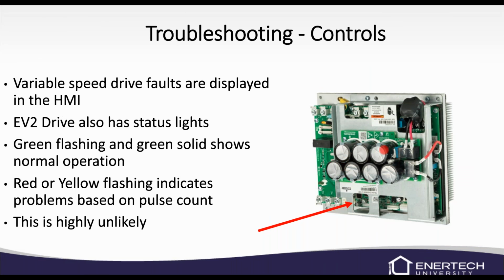This is the variable speed drive for the compressor here, and it does have status lights. Green flashing and green solid show normal operation. The red or yellow flashing indicates a problem that's based on pulse count. I do not know what those pulse counts mean, so if you do get that, just write it down and give me a call, and I'll get in touch with Jeff Croxall, our engineer, and see what he has to say about it. It's not very likely. I don't know that I've had one of these EV2 drives fail. Not that they can't, but I don't know that I've had one yet. So that's a good thing.